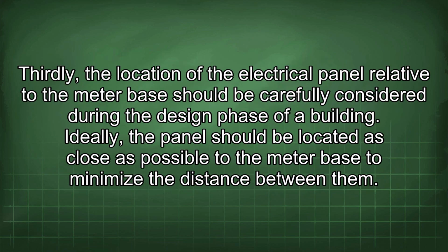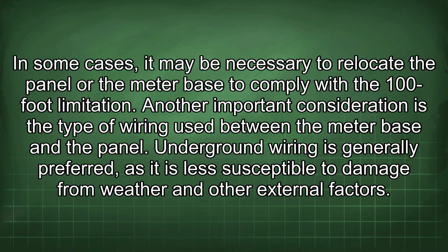Thirdly, the location of the electrical panel relative to the meter base should be carefully considered during the design phase of a building. Ideally, the panel should be located as close as possible to the meter base to minimize the distance between them. In some cases, it may be necessary to relocate the panel or the meter base to comply with the 100-foot limitation. Another important consideration is the type of wiring used between the meter base and the panel.